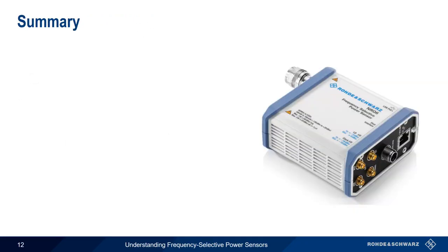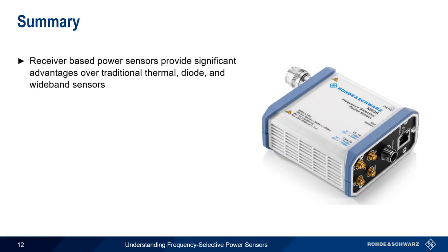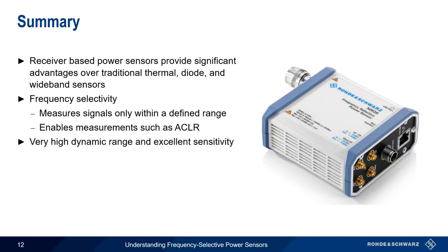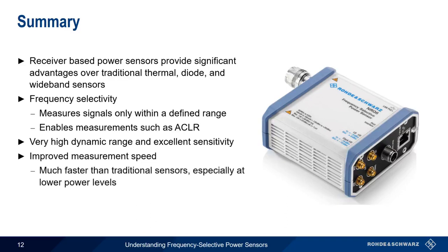So let's summarize what we've learned. Receiver-based power sensors, such as the Rohde & Schwarz NRQ6, provide significant advantages over traditional thermal, diode, and wideband power sensors. These advantages fall into three main categories: the first is frequency selectivity — frequency selective sensors measure signal power only within a user-defined frequency range or filter width, and this also enables frequency-specific measurements such as ACLR. Additional advantages are very high dynamic range and excellent sensitivity. And finally, receiver-based power sensors have greatly improved measurement speed — not only are they much faster than traditional sensors, but this improvement is even more dramatic at lower power levels. This concludes our presentation, Understanding Frequency Selective Power Sensors.